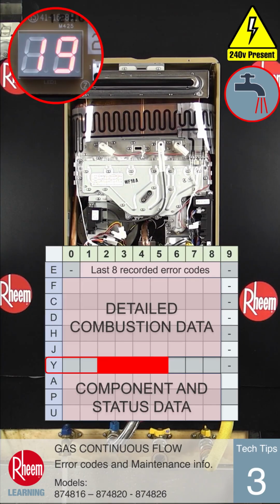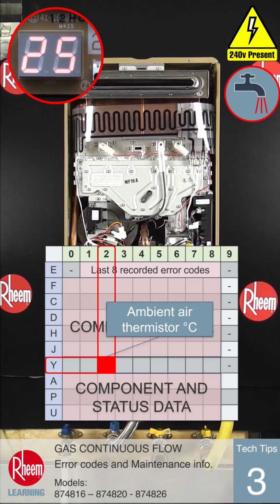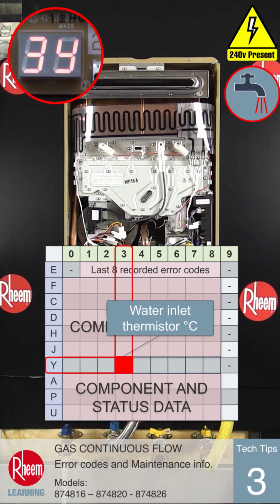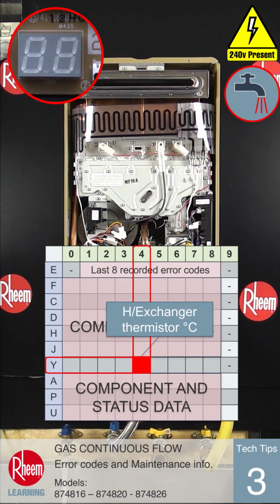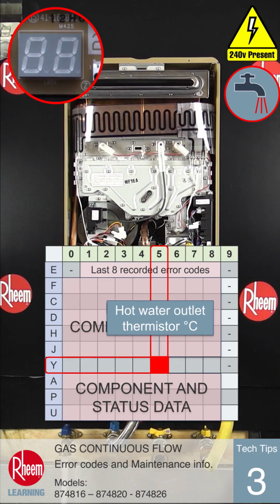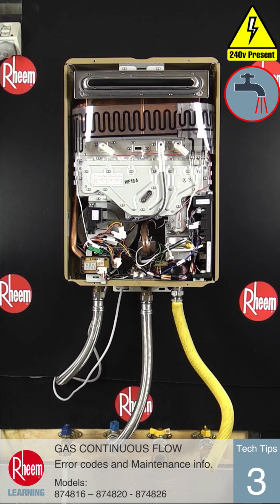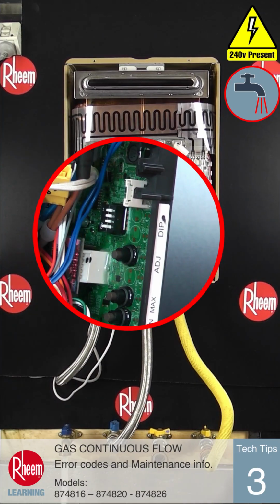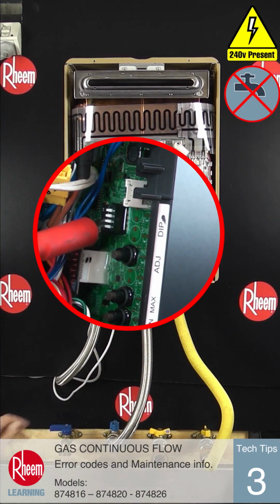The next 4 boxes on the table in this line have the live temperatures from the temperature thermistors. 2Y is the ambient air temperature. 3Y is the inlet cold water temperature. 4Y is the heat exchanger temperature. And 5Y is the hot water outlet temperature. To return the unit to normal operation, just turn off dip switch number 1 at any time.